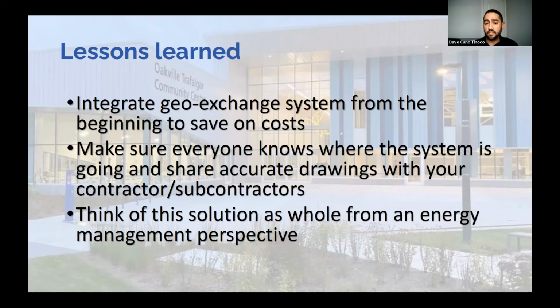Third, think of this solution as a whole from an energy management perspective. Although it greatly reduces carbon emissions, it does use more electricity to run the heat pumps and auxiliary equipment. To complement energy use at the facility, the town considered a solar PV system. We're installing a 250 kilowatt DC system, with another 250 kilowatts planned for an adjacent parking garage. Once fully implemented, this 500 kilowatt system would provide enough electricity to power the system entirely and then some, giving us a truly net zero energy, very low carbon heating and cooling facility.